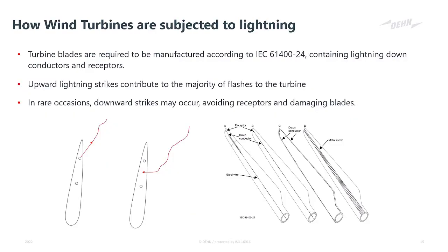Now, I mentioned that lightning protection is implemented into wind turbines during manufacturing. How this lightning protection system works is that the turbine itself will have a foundation earthing system, and then that would be connected to the base of the turbine, either as a reinforced turbine with reinforcing, or a metallic base and tower system as well. And then at the top, inside the blade, you will have a lightning down conductor. There are different designs between different manufacturers. You can see this one is on the outside of the blade, and some of them are in the middle. But there are requirements in IEC 61400-24 on how to implement this.